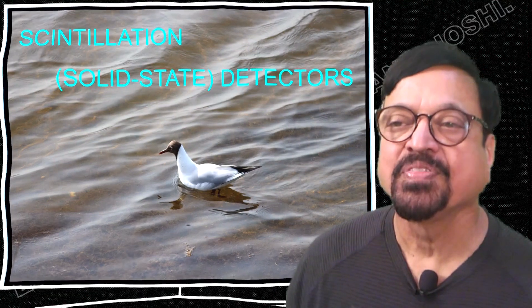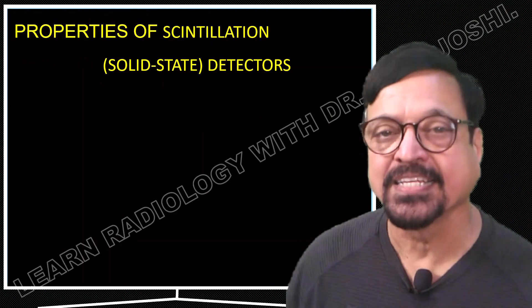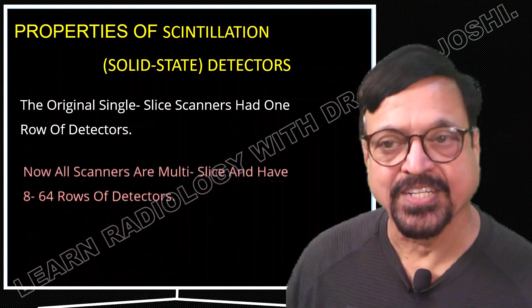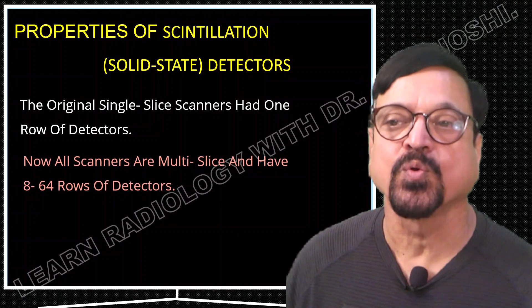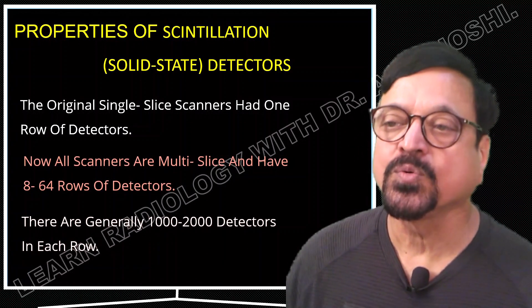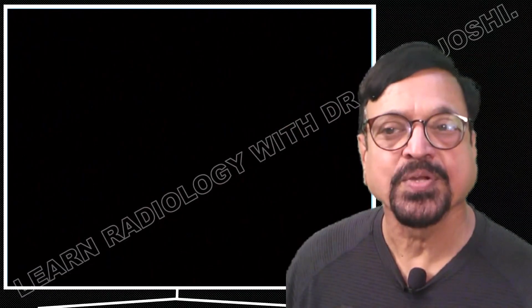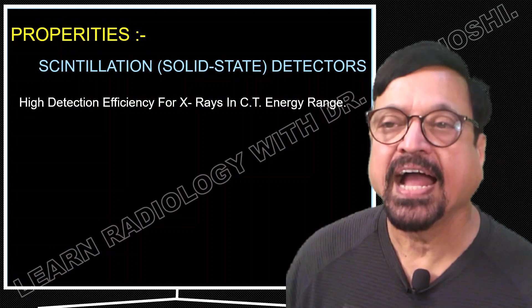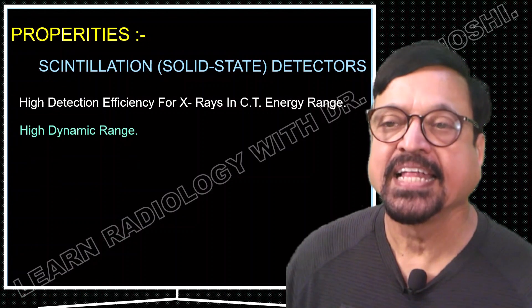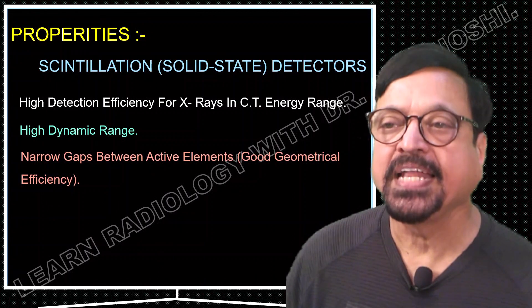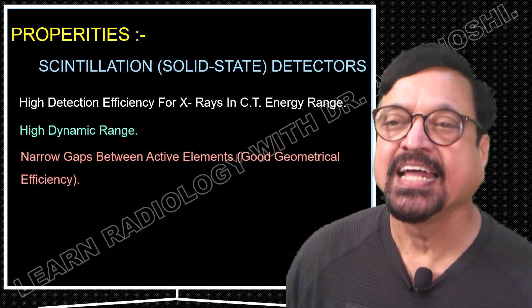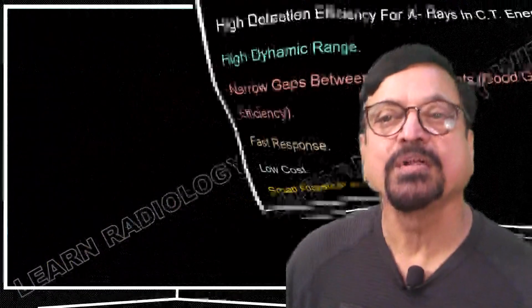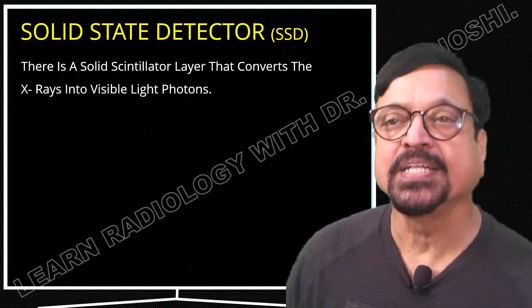Solid-state detectors are used in all modern machines today. The original single-slice scanner had one row of detectors, but all current scanners are multi-slice with 8 to 64 rows of detectors depending on machine design, and generally 1,000 to 2,000 detectors in each row. Because they are small in size, more can be fitted. Scintillation solid-state detectors offer high detection efficiency for X-rays in the CT energy range, high dynamic range, narrow gaps between active elements (good geometric efficiency), fast response, low cost, and small physical size — allowing more detectors to be fitted to increase resolution.